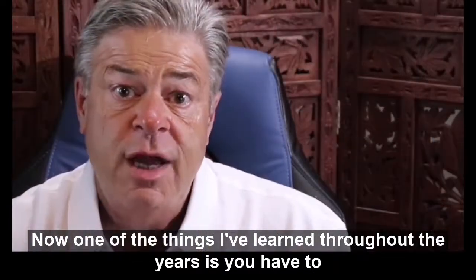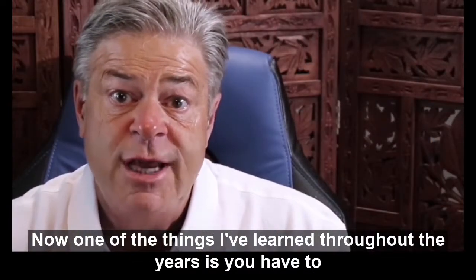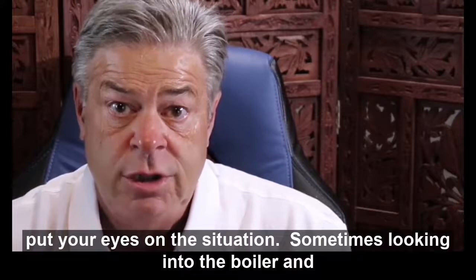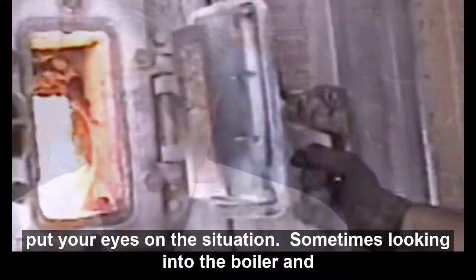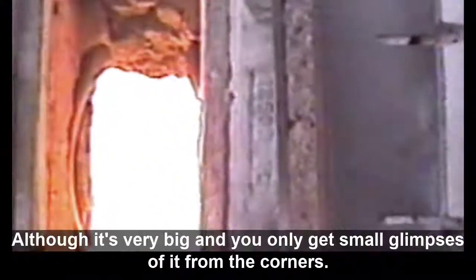Now, one of the things I've learned throughout the years is you have to put your eyes on the situation. Sometimes looking into the boiler and observing the combustion process, although it's very big and you only get small glimpses of it from the corners, it can be very revealing in terms of looking at what could be going wrong with our combustion process. Sometimes I don't even need to do the engineering or technical measurements associated with a power plant to know that there's an issue.